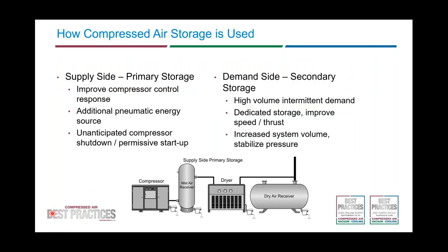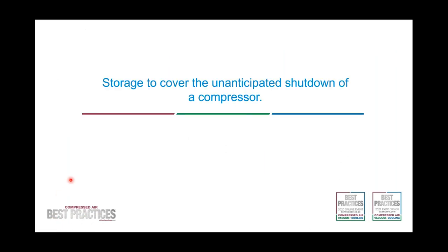So how can we use receivers? We can use them on the supply side — primary storage — to improve compressor control for load-unload lubricant-injected rotary screw compressors, provide pneumatic energy, and cover situations such as a compressor shutdown where it takes time for a standby to come on. On the demand side — secondary storage — we address high-volume intermittent demands, dedicated storage for a particular end use, and simply increasing system volume to stabilize pressure overall.